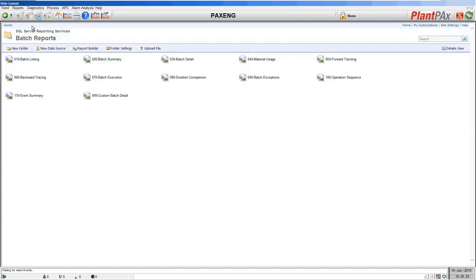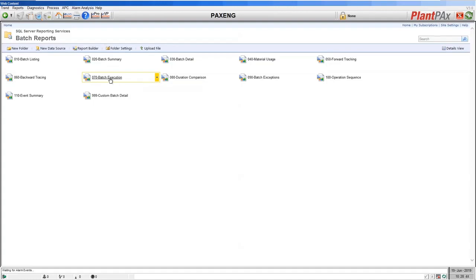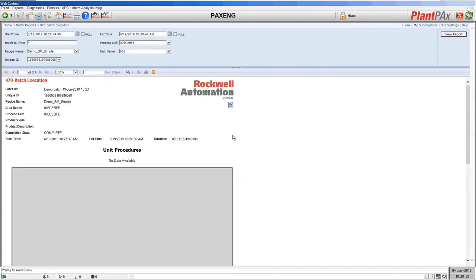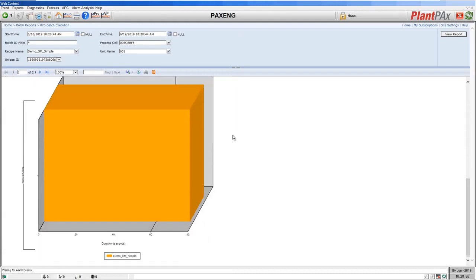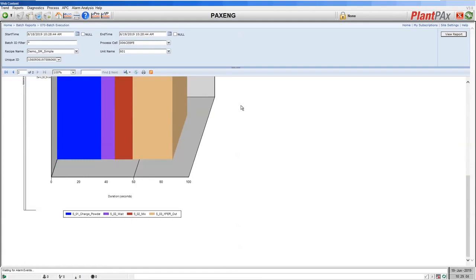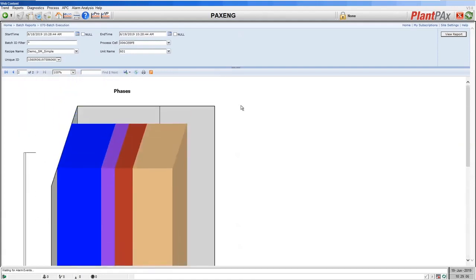The next report available in Sequence Manager is the batch execution report. The material usage forward and backward tracing are only available if you move on to FactoryTalk Batch in the future. Batch execution shows you the timing of a sequence that you ran. Here we can see for this demo sequence that we had a single operation, and on the second page we can see the timing of those equipment phases run by Sequence Manager — useful for seeing where time is being used and where you might improve things.